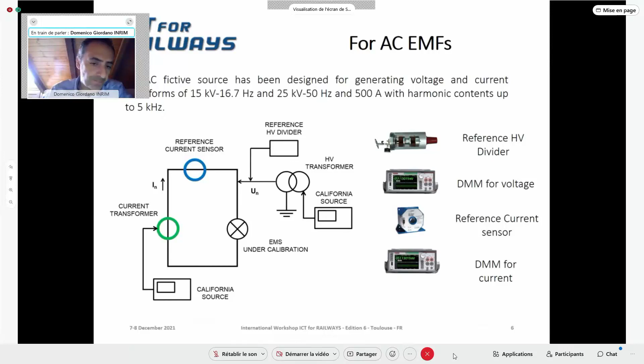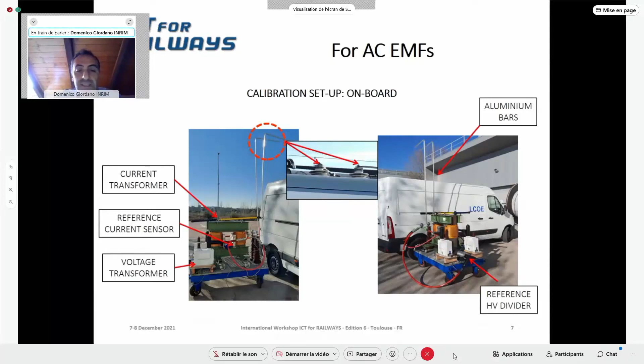Here is an example of a possible upgrade of the system that can be applied in the laboratory for calibration of the energy measurement function, even on board. The idea is to perform calibration and periodic re-verification of the accuracy of the energy measurement function directly on board by applying a phantom power. So we apply voltage and current, but it's not real power, though from the energy measurement function's point of view it's like seeing real power. This way, we are able to apply reference signals that allow calibration. Here you can see the proposed setup for AC calibration.